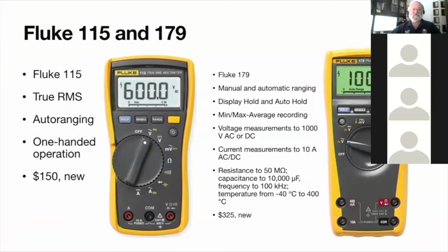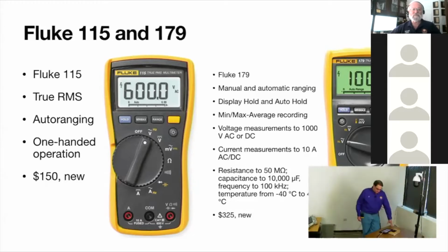One of the things I find very valuable is the fast ranging bar chart on the bottom. When you're looking for something intermittent or jumping around, digital meters are slow sampling, often just once per second. So there's no way you can find something intermittent, or in the case of a pulsed transmission, see how much the voltage is dropping during a short current load, maybe when the transmission pulses. But it's very valuable to have that bar chart on the bottom of the Flukes, because although you can't get an exact value from it, it's very fast sampling.